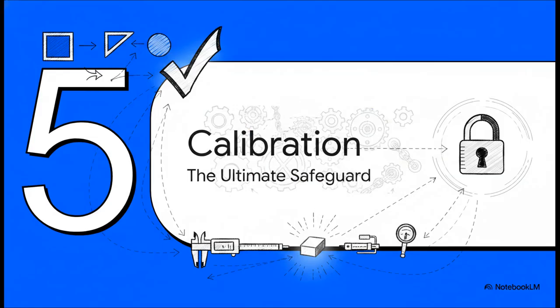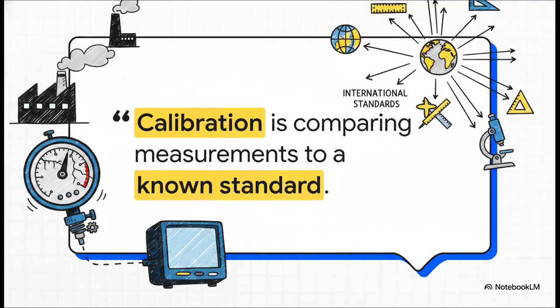Section 5. The importance of calibration. So, the crucial point is none of this, literally none of the tools or properties we've discussed today matters at all if we don't have a way to verify them. Let's look at the core definition here. Calibration is the process of comparing the measurements from an instrument to a known standard to ensure accuracy and reliability. This is the magical link, right here. Calibration is how we take a single, isolated gauge on a dusty factory floor and mathematically connect its accuracy all the way back to perfectly maintained international standards.